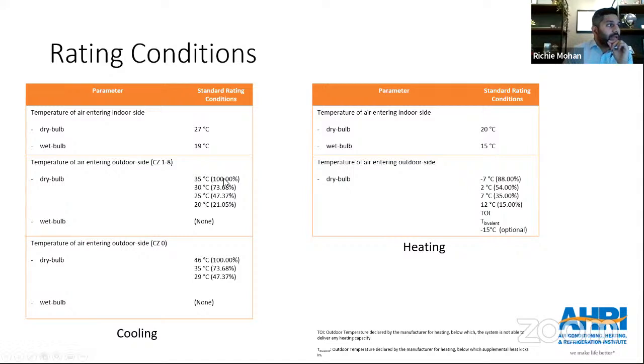Subsequently, we look at the outdoor ambient temperature, which becomes important because every region has a different take on what the outdoor ambient needs to be. We looked at the various regional VRF standards as they stand today: AHRI 1230, the US-based VRF standard; EN 14825, the European VRF standard; JIS B8616, the Japanese standard for VRF; and the Chinese standard for VRF, which is pretty much in alignment with the ISO standard.